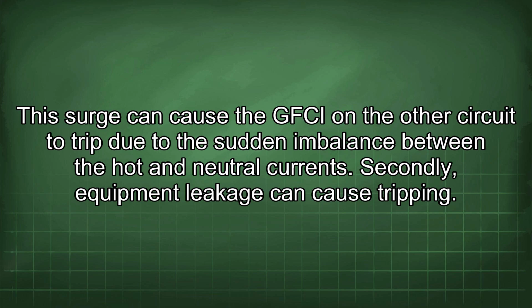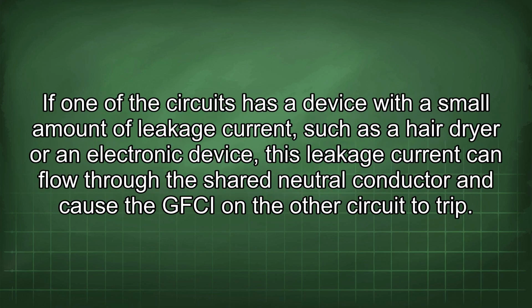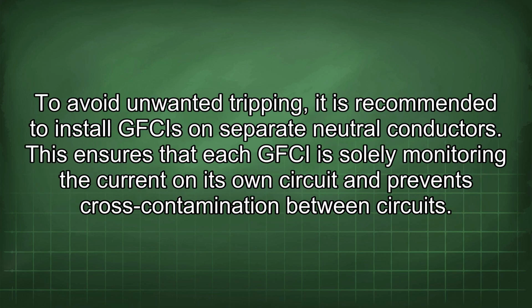Secondly, equipment leakage can cause tripping. If one of the circuits has a device with a small amount of leakage current, such as a hairdryer or an electronic device, this leakage current can flow through the shared neutral conductor and cause the GFCI on the other circuit to trip. To avoid unwanted tripping, it is recommended to install GFCIs on separate neutral conductors. This ensures that each GFCI is solely monitoring the current on its own circuit and prevents cross-contamination between circuits.